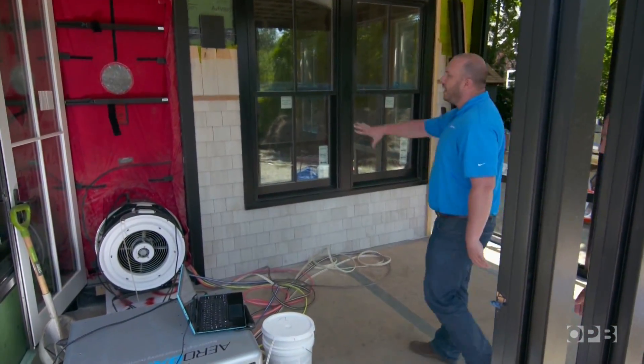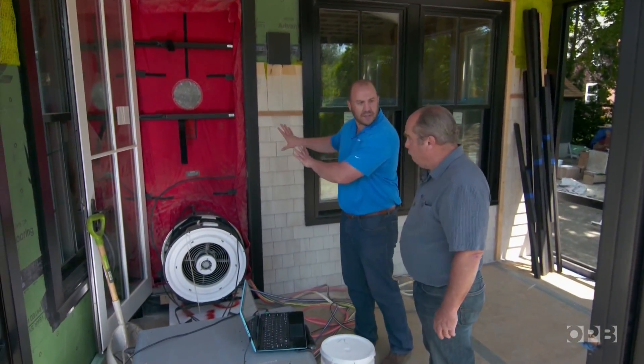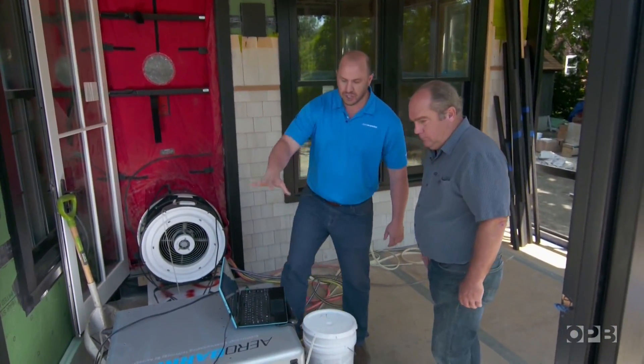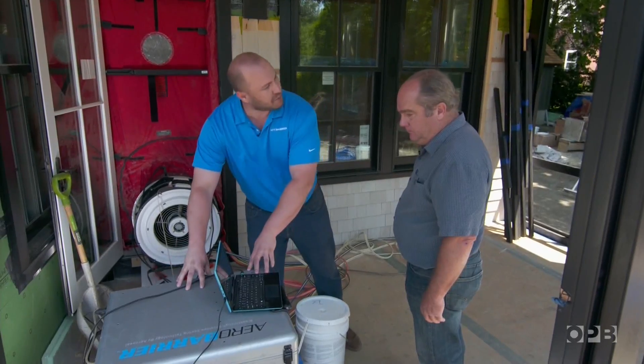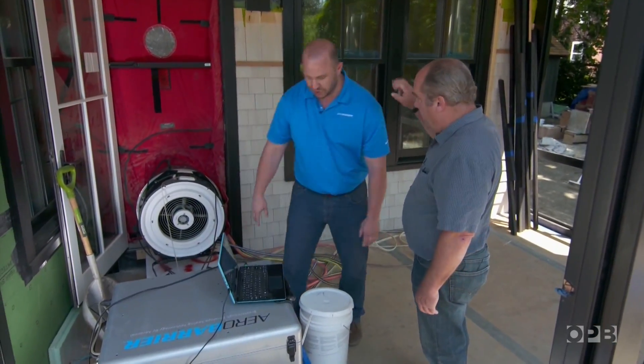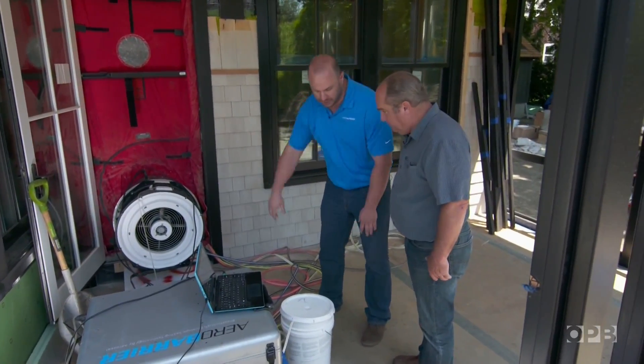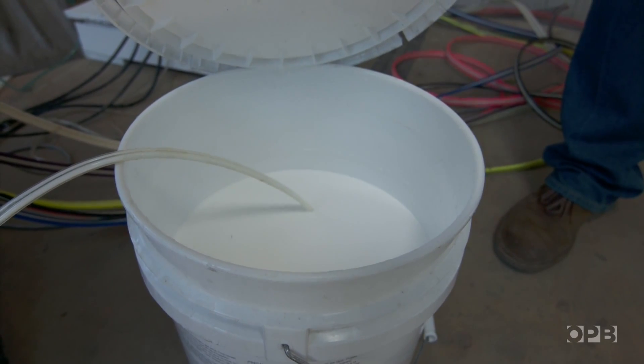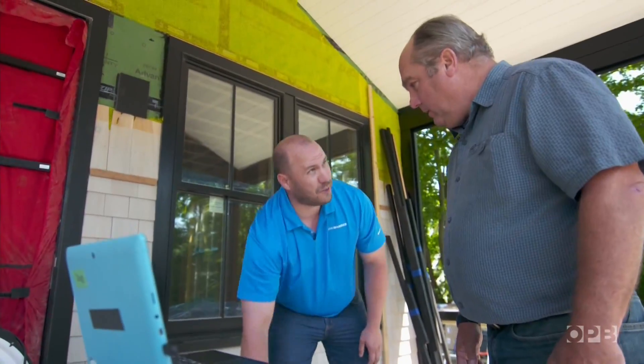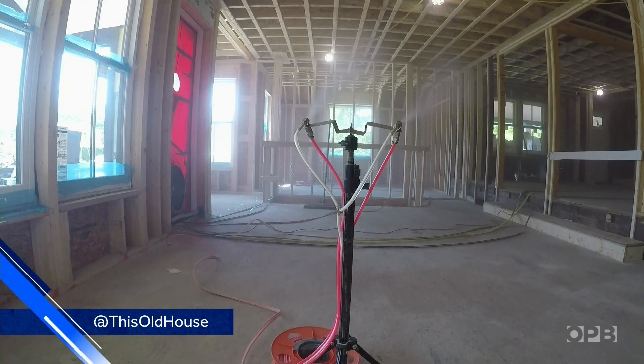Here's the basic setup. Here's our blower door — the fan right there — which we're going to use to put the positive pressure in. Here's the laptop that's controlling the whole system. This is a pump system inside this box that's going to spray the material in — it'll pull the material and pump it through the lines to the spray nozzle. And this is the actual material right here; it looks a little bit like paint. How long will it take to pressurize and seal it all up? About 90 minutes.